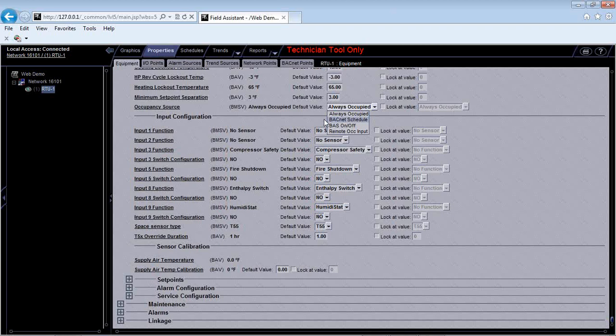Just general overall occupied versus unoccupied is just for general standard night setback. What it does is you have set points for your occupied period and you have different set points for your unoccupied period. So for energy savings, if you want to maintain 70 degrees and 75 degrees when people are in the building and it is occupied, those would be your occupied set points. If you just want to maintain the building at 60 degrees and 80 degrees during unoccupied periods, you would set it up so that it had those broader set points. I think everyone's probably familiar with that, just in case.